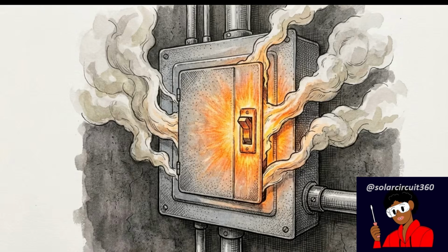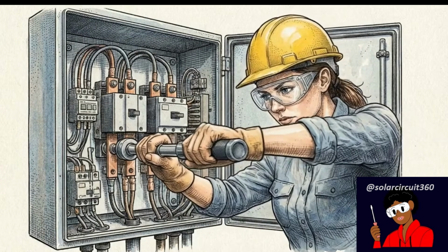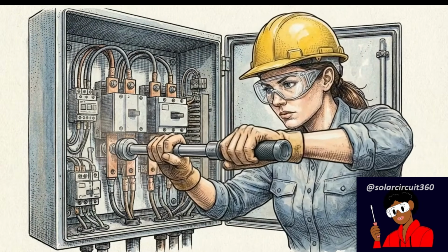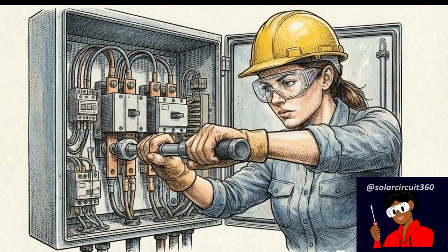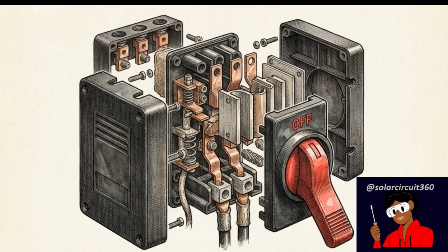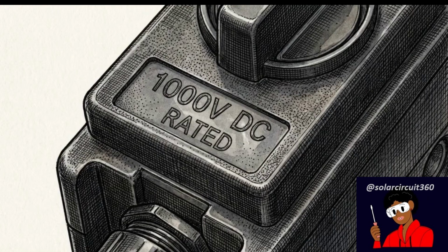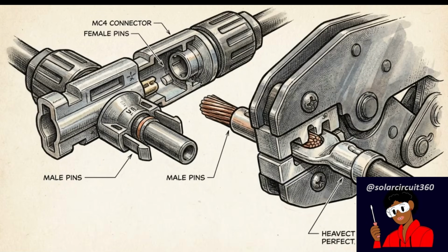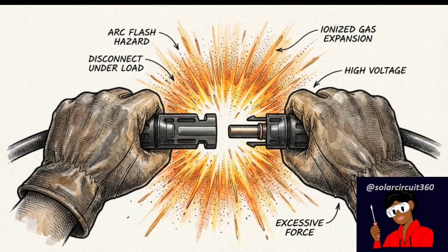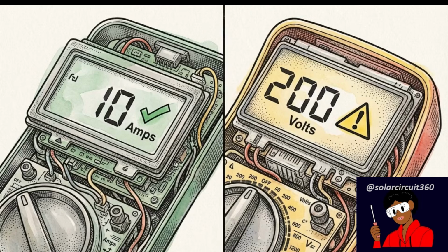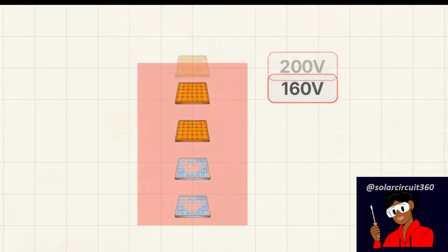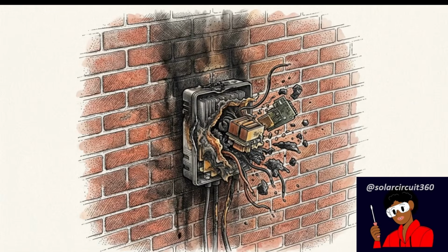fire hazard. To safely operate high-voltage arrays, we must practice prevention engineering, utilizing strict, deliberate steps to stop arc initiation before it begins. The physical requirements for a safe array are absolute. You must utilize properly rated DC disconnects and ensure every MC4 connector is perfectly, professionally crimped to eliminate microscopic gaps. And the golden rule for installers is to never isolate or disconnect a live circuit while it is carrying an active load. In solar engineering, fearing only the current is a fatal mistake. You have to respect the hidden math of voltage stacking, because voltage provides the spark, but time guarantees the fire.